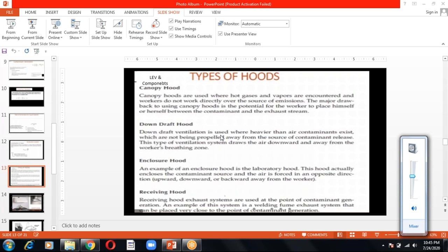I think Mr. Jawad can answer this next question, because I feel yesterday we were discussing something related. According to OSHA 1910.94, ventilation, a paint spray booth operation should provide enough dilution air to reduce the vapor of flammable material to blank percent of the lower explosive limit. It is asking 10%, 15%, 20%, and 25%.